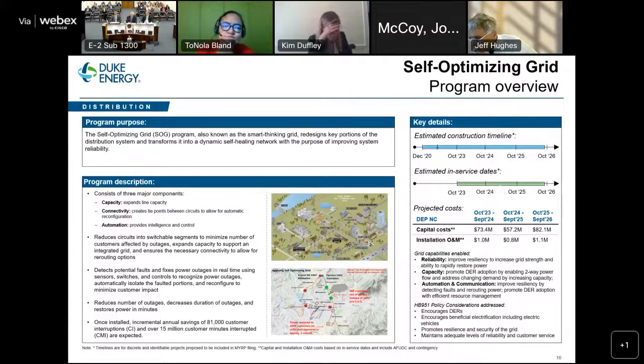One last piece of information: between those two green switches where the fault is, there are 488 customers that have a sustained outage until a crew can respond, find the problem, and fix it. Before self-optimizing grid was placed on these two circuits, that same fault event would have resulted in 2,691 customers having a sustained outage. So from 2,691 customers down to 488 — that's what self-optimizing grid can do for us and our customers.